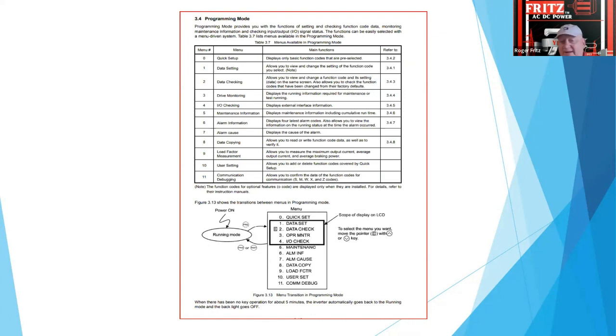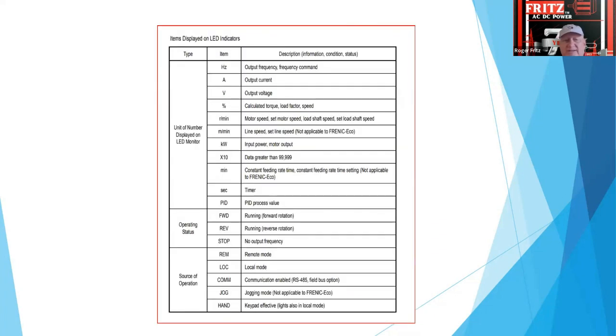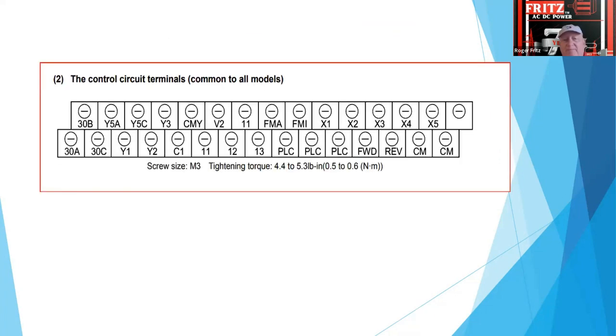They have a lot of data screens you can set up. You can scroll into them, all the various inputs, outputs. This is the control circuit, that shows they put a DC power supply in here. So it has like 24 volt power output. Then you can select through the keypads all the digital inputs of what they're doing, which analog signal you're drawing back from, if you're putting it in a pump application for PID loop, or those things.